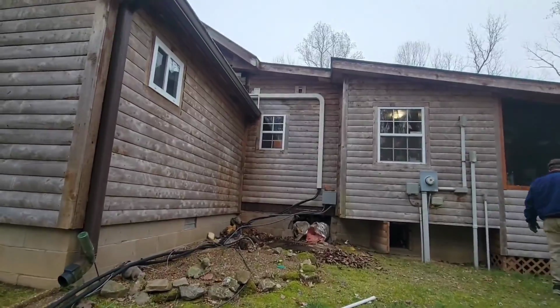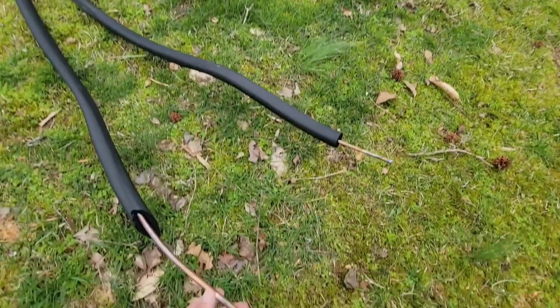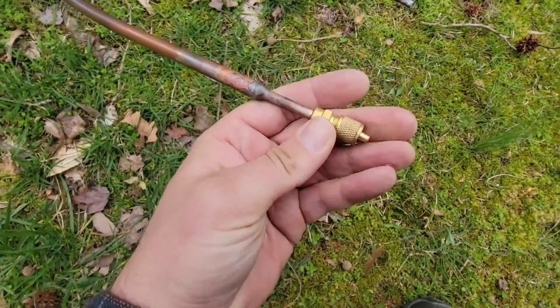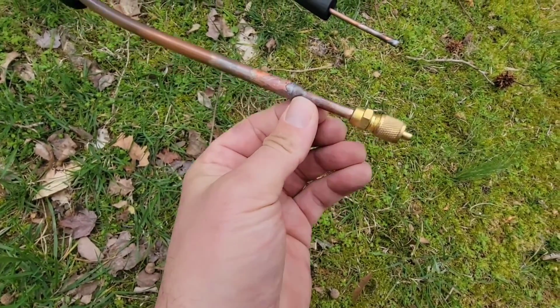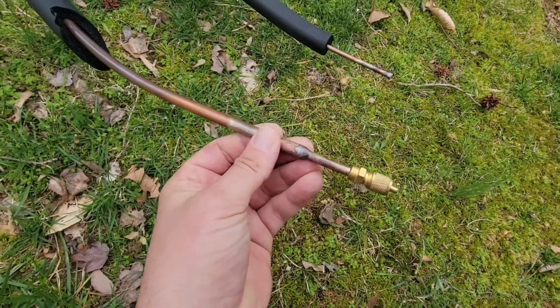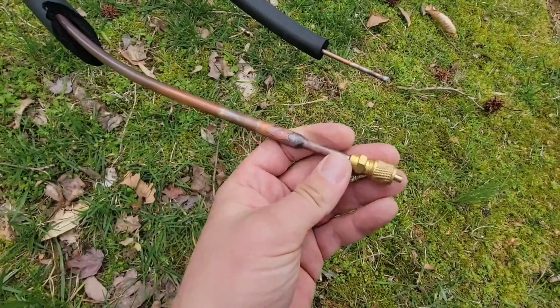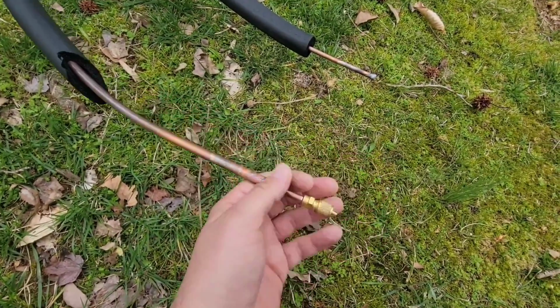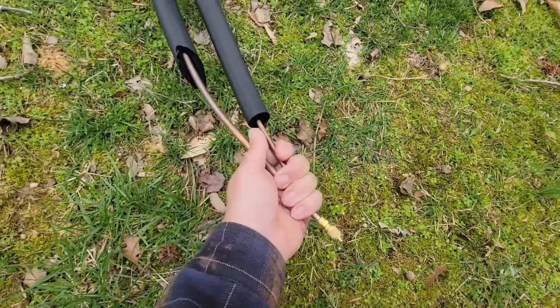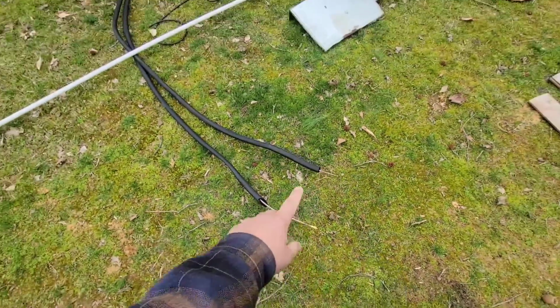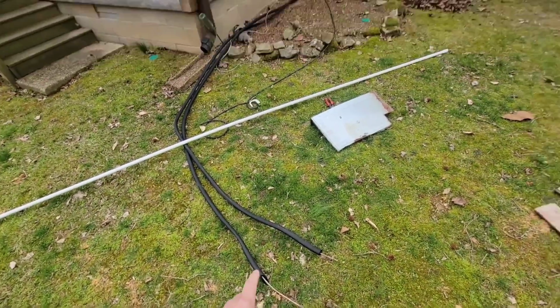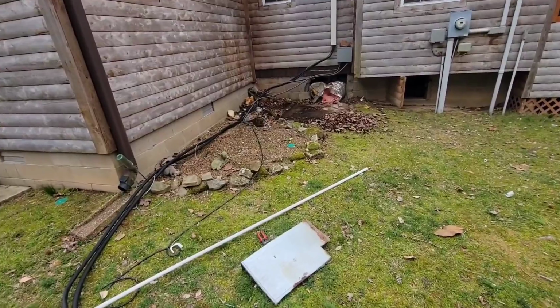So after roughing in the line sets and line hide cover for that upstairs wall mount air handler, they've got a service access fitting connected to the 3/8 vapor line, and they've got nitrogen on it. So they'll keep nitrogen on this until they put the flare fittings on and connect it to the outdoor unit.